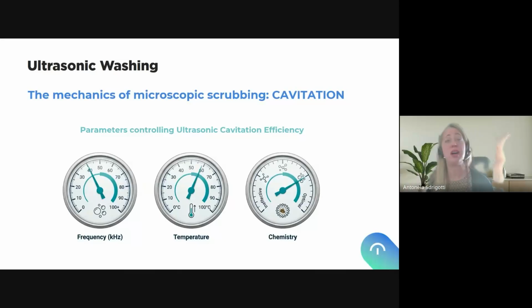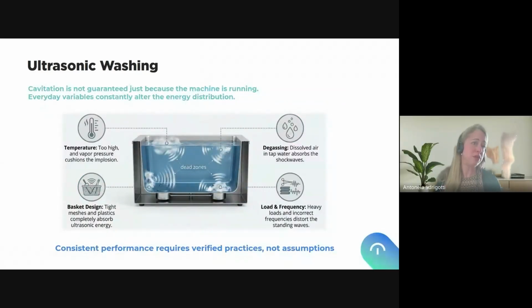Temperature also cannot be too low or too high, because this will provoke a difference in the cavitation energy, and the chemistry also, because everything dissolved in the water will affect the cavitation energy. And why is it very important to monitor the cavitation energy? Because the cavitation will not work just because the machine is running. Every day, and I would say every time we change the solution, the parameters or variables can change and the energy distribution can be different.